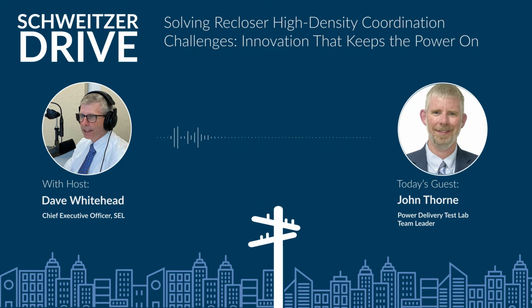But to that point, in today's world, it's not acceptable to just stop the current flowing from somewhere. We want that selectivity. We want the right device to trip so the least number of customers are impacted. That's what this high-density coordination allows us to do, moving to that next step, leveraging modern communication networks, modern protocols, and modern computing power in our distributed equipment out there on the line, allowing us to do something really powerful.